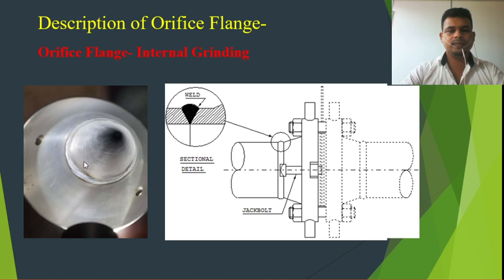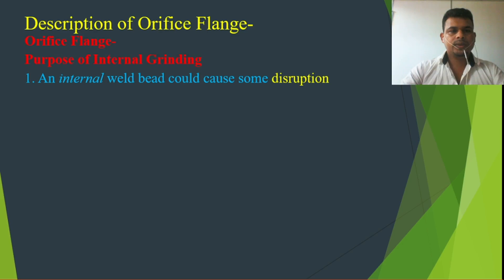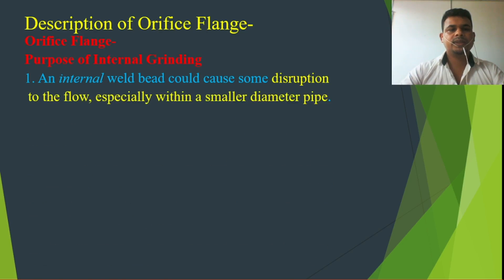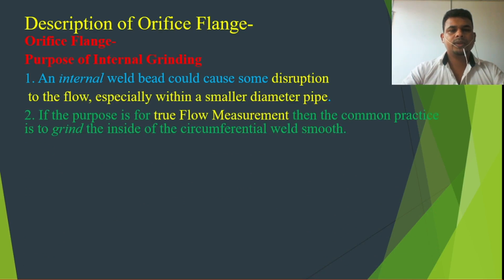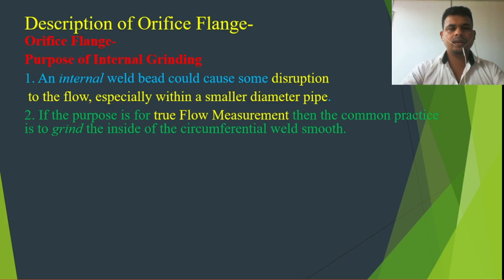The purpose of internal grinding: an internal weld protrusion could cause disruption of the flow, especially with smaller diameter pipes. If the pipe is small diameter and the welding is very near and the root protrudes, it causes some disruption during water or gas flow. Also, if the purpose is for true flow measurement, then the common practice is to grind the inside of the circumferential weld smooth.